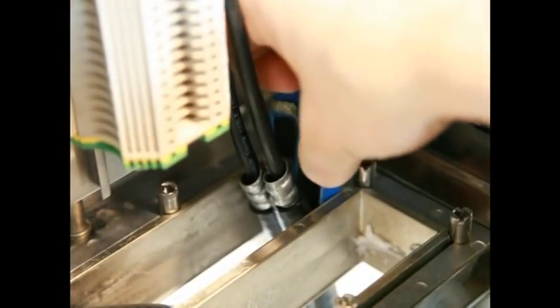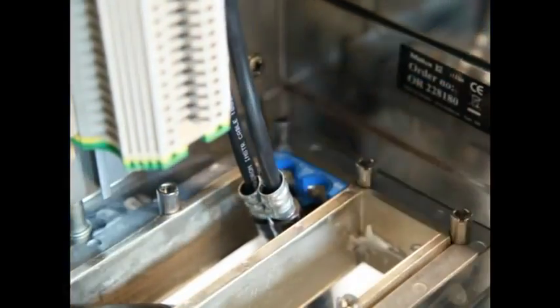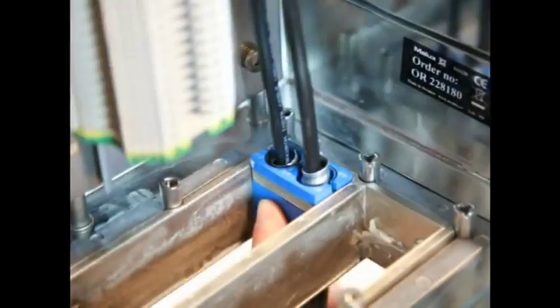Insert the module halves around the cables from the inside of the opening and push them towards the outer edge of the frame. Make sure that the braid is in contact with the armor.